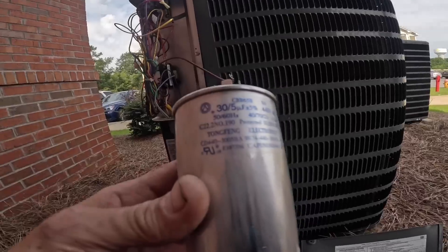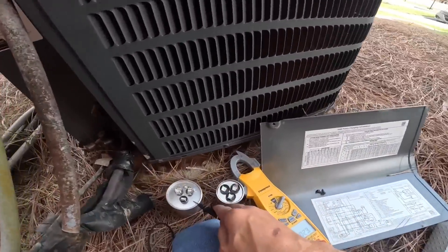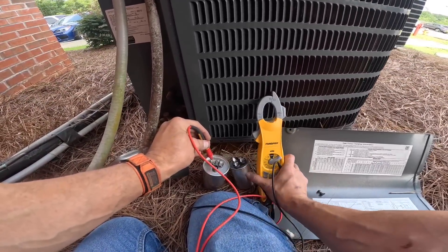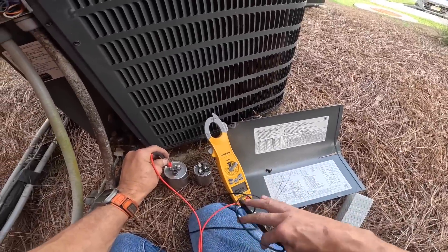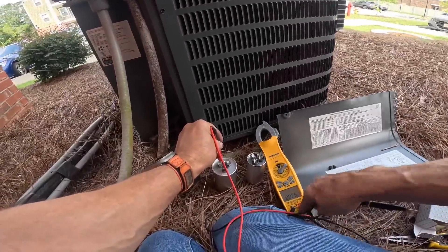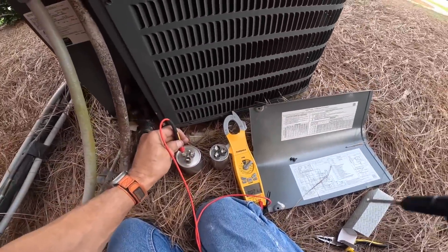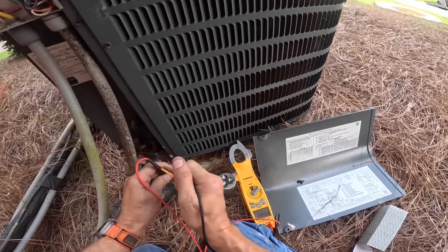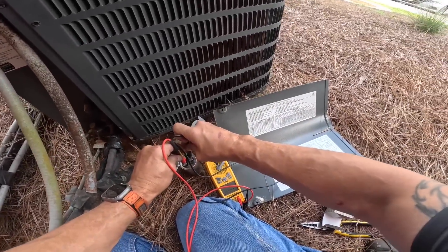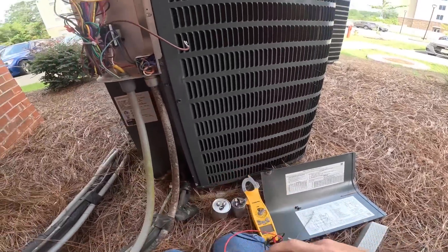It's a 30 and 5 — let's go get one. Alright, let's test these. That's the old one with that little bubble on it, this is the new one. It's supposed to be a 30 and 5. 30 on the herm, five on the fan.